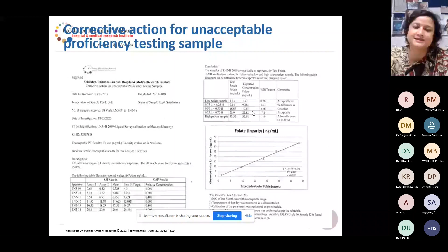Or you can take the new calibration lot and then you take the previous linearity survey samples, and sometimes that also is one of the procedures. So these are some examples.